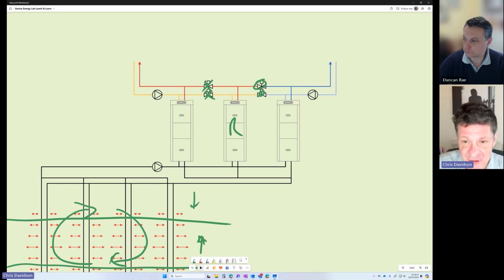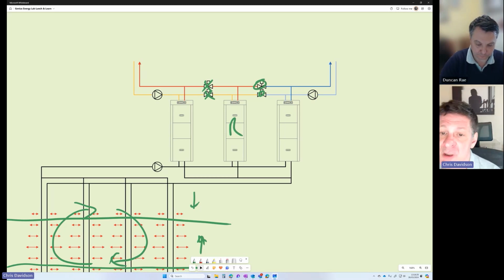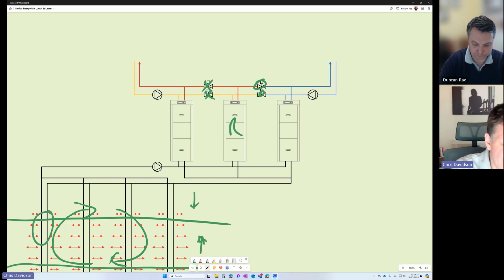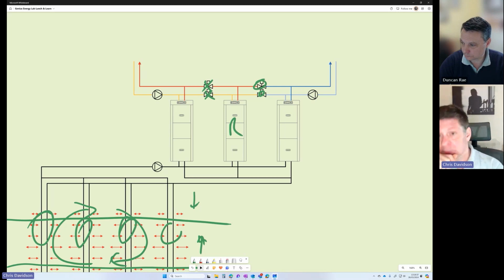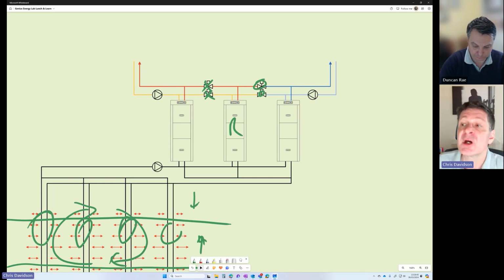We need to understand the nature of those loads, and that's not just for the ground loop model. We need as a minimum monthly load profile breakdowns for a ground loop model. Ideally, we'd have hourly, and we are increasingly working on hourly models, but monthly is a minimum. And we not only need to understand that in terms of modelling how much pipe we need to put in the ground down here, but also to understand the nature of those loads so we can select our heat pumps. We've got to select the appropriate number of heat pumps with the appropriate number of stages so that we can accurately match those loads. And thinking of a number and doubling it isn't helpful as far as sizing heat pumps are concerned, like you used to do with boilers.